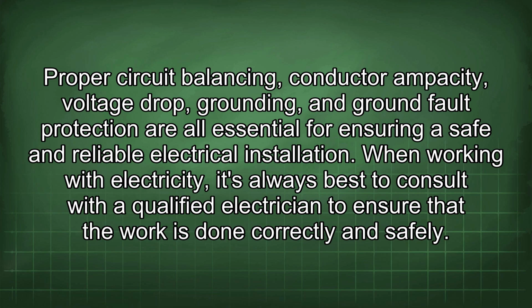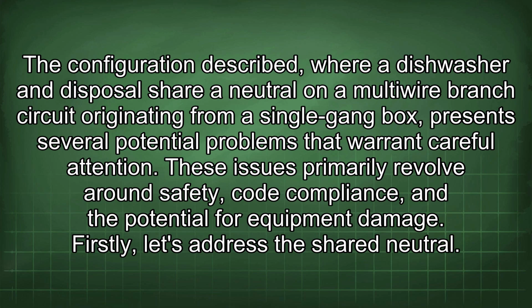The configuration described, where a dishwasher and disposal share a neutral on a multi-wire branch circuit originating from a single-gang box, presents several potential problems that warrant careful attention. These issues primarily revolve around safety, code compliance, and the potential for equipment damage. Firstly, let's address the shared neutral.